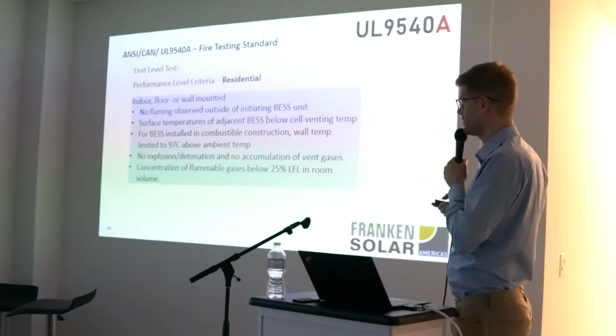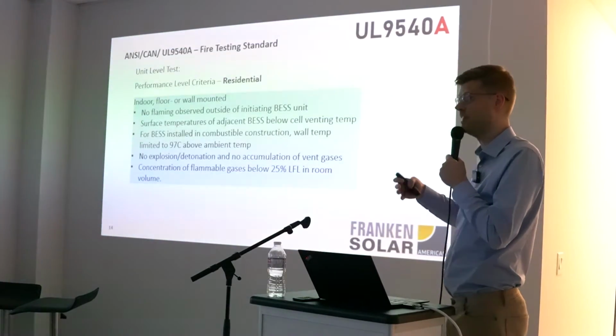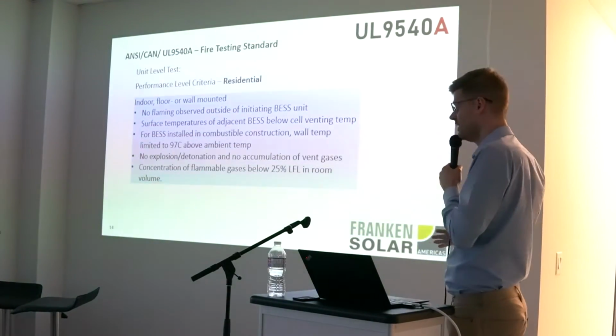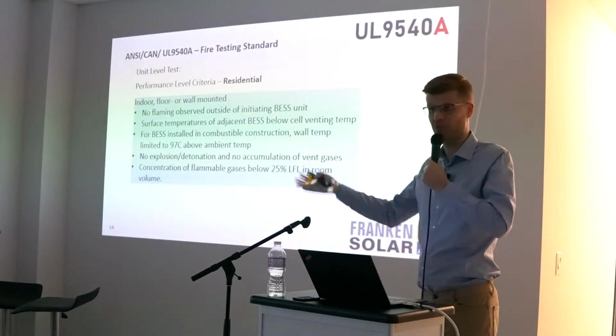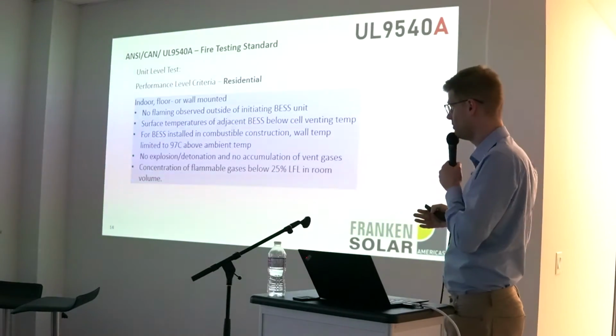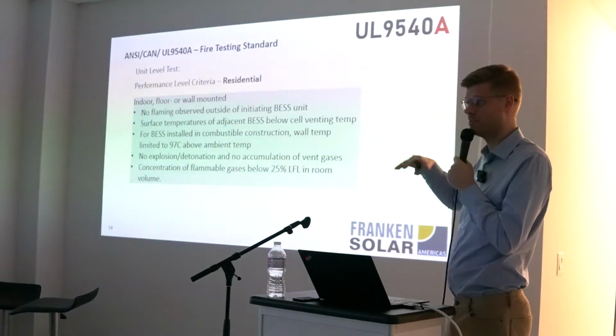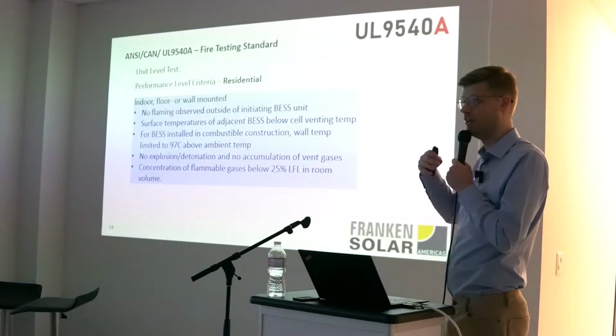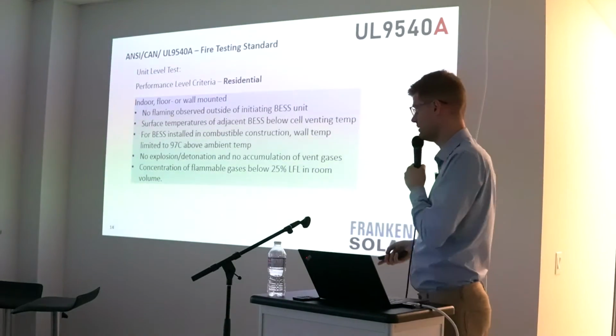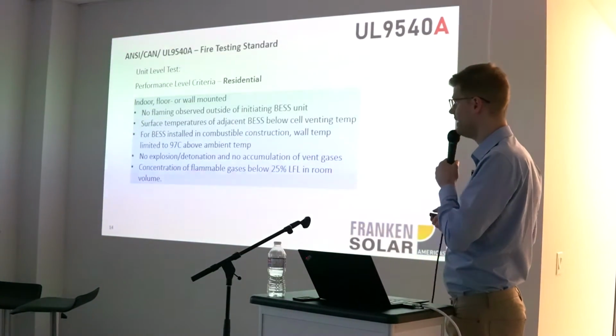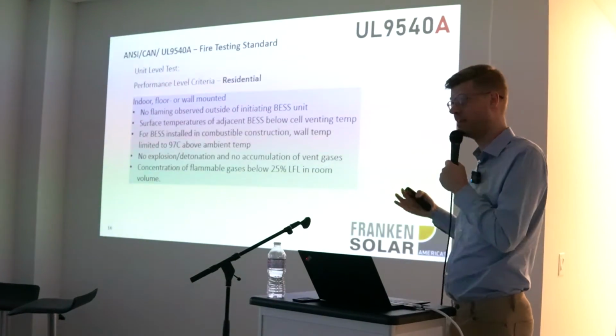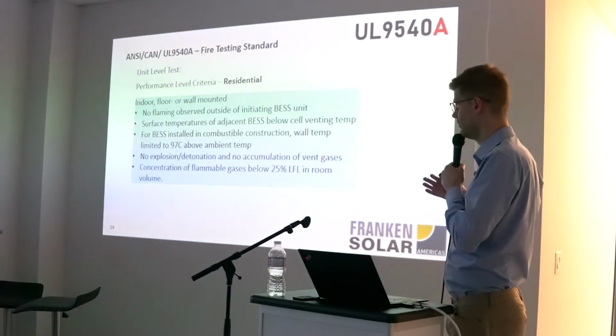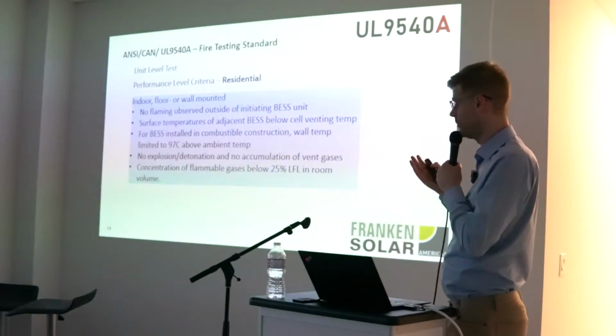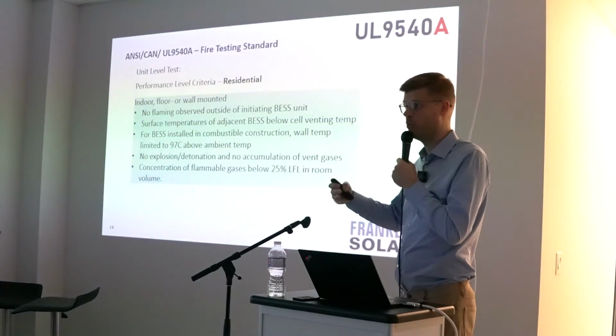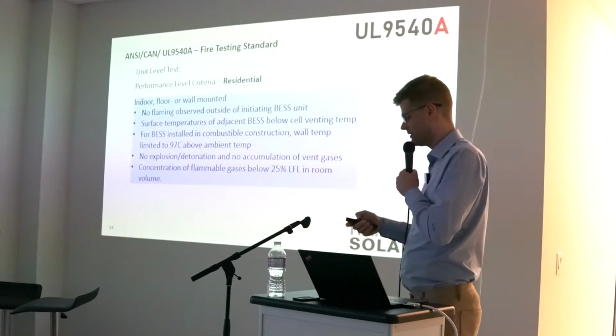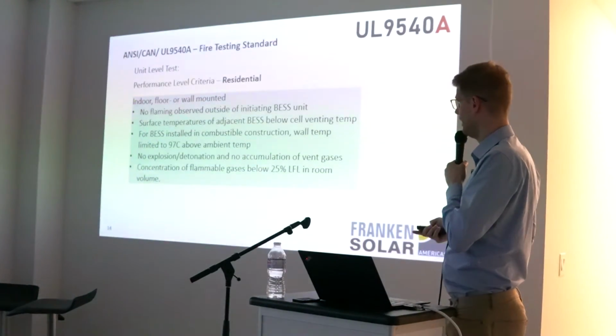The combustible construction criterion: if the system gets hotter and hotter, it cannot ignite surrounding material. For example, if you have a cabinet in front of a wooden wall or a studded wall or whatever you have in your basement or any room in your building, the temperature cannot exceed 97 degrees beyond the ambient temperature, just to make sure that there's not excessive heat being put into the environment and the walls. And you cannot have any concentration and accumulation of flammable gases within that cabinet that exceed a certain level, in this case 25% of the lower flammable limit in the volume of the room, so that the room will never have any explosion where these gases could ignite and cause a problem.